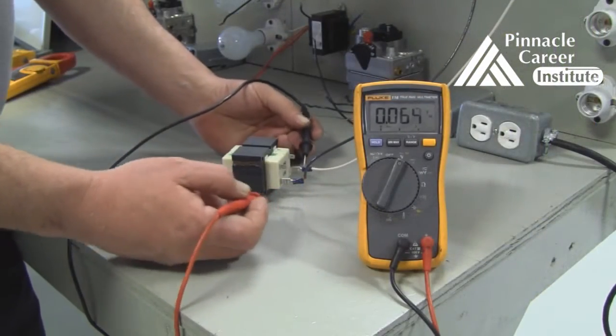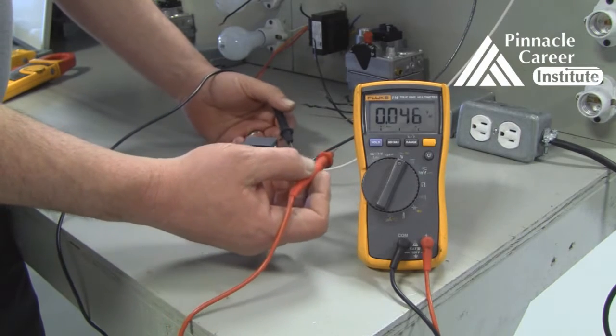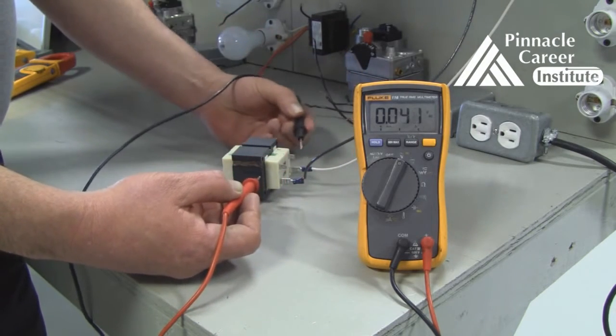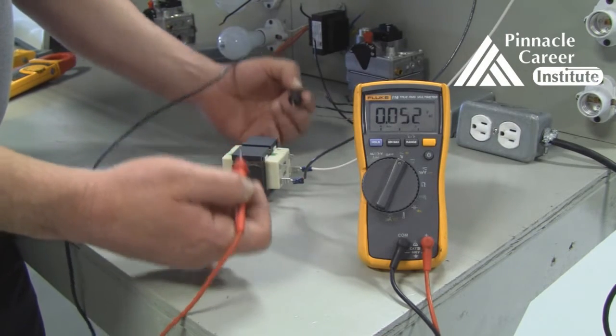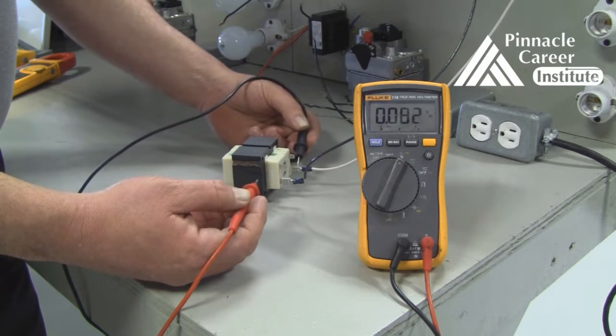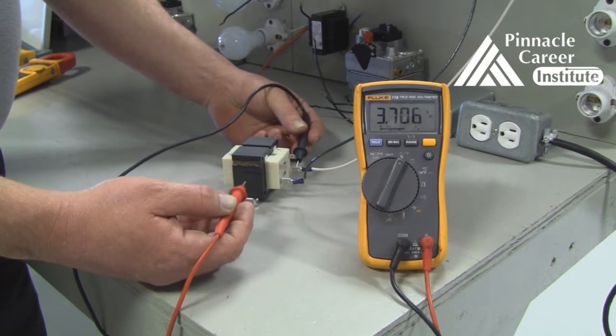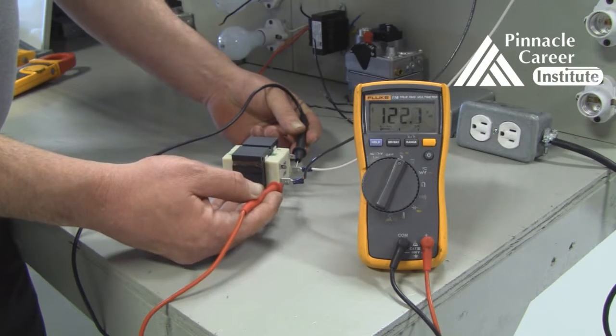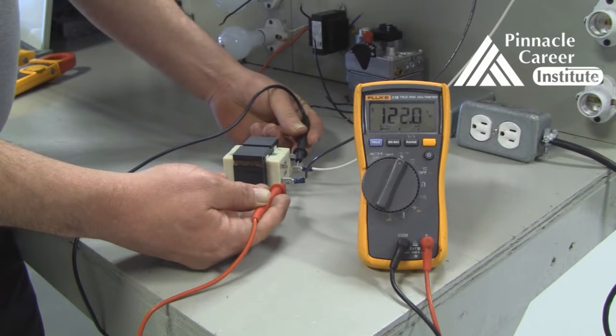So now we're going to test voltage on a component. We have a normal transformer here. You can see the black or 120 volt wire coming in and the neutral wire coming in. When testing voltage on a component, it is always very important to have a neutral or that white wire. So I'm going to place one meter lead on the neutral and one on the 120 volt hot. And you can see here I have 122 volts.